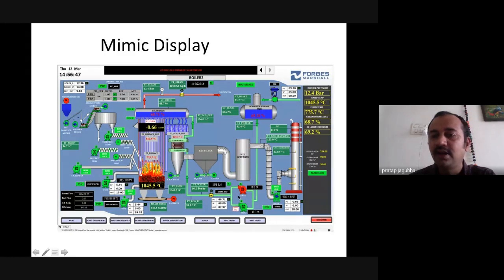This is the typical control available from a computer control of one typical DCS for boiler house control, where you can see it's a solid fuel control where the furnace temperature is around 1045. The draft pressure is controlled near 0 mm water column, which is the ideal scenario. Draft is controlled between the FD and the ID fans, and balanced at the middle section of the furnace. Then there are the drum level control, the pressure control, and the oxygen control. All these parameters are put together simultaneously, giving a better representation. Any layman can easily understand it, modify the set point, and become well versed with the boiler control.